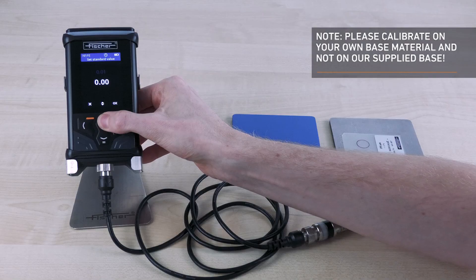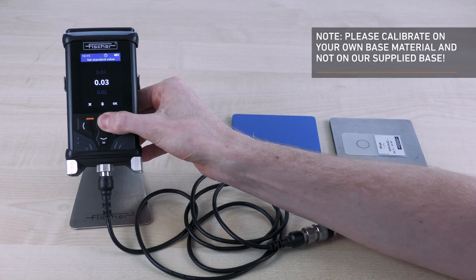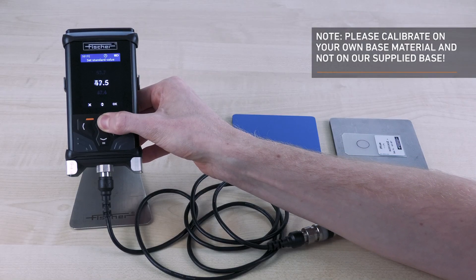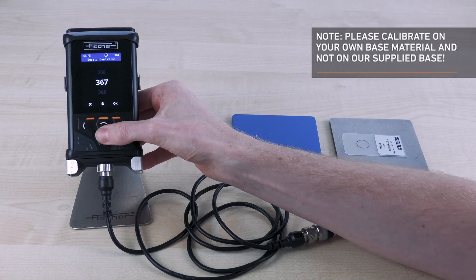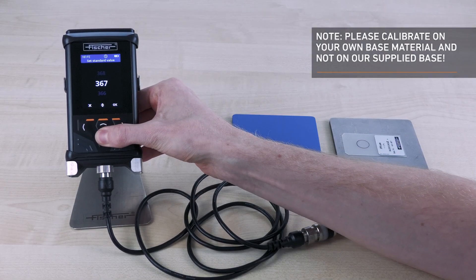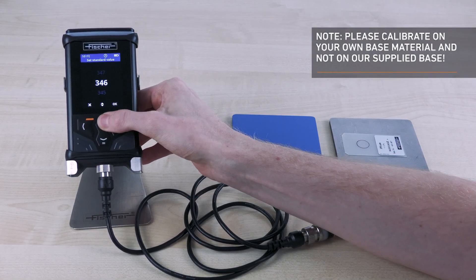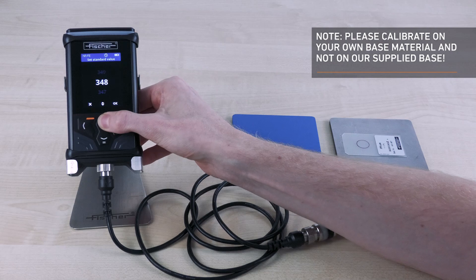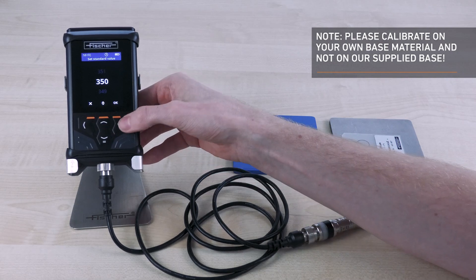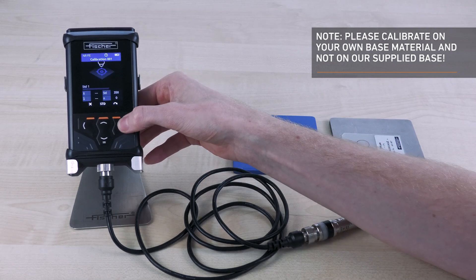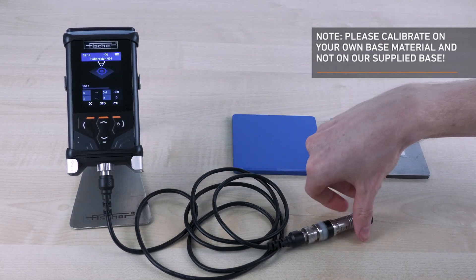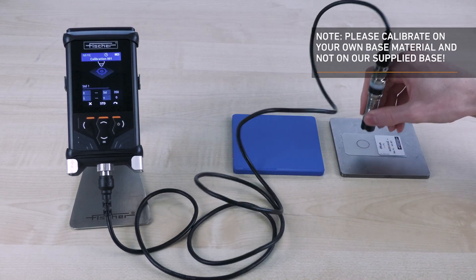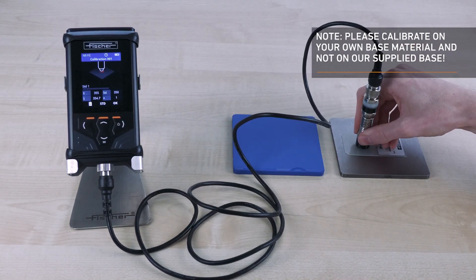Click on the up arrow key to set the target value of the calibration foil. Then place the calibration foil on the uncoated test part and perform at least five measurements again. Then confirm with two times OK.